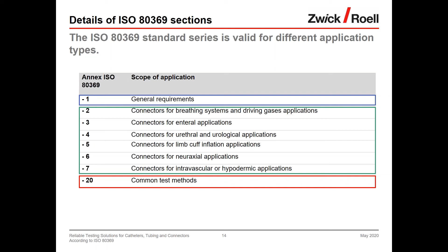If we are talking about the most common one, the ISO 80369-20, it is important to know that each specimen has to be assembled according to the standard with a suitable reference connector before the test sequence starts. In the past, these two test sequences had to be carried out separately. The big advantage of the ZwickRoell solution is that the workflow can now combine these steps, assembly and testing, in one procedure. I already heard from our customers that they save time and reduce failures by repeated handling of samples, and therefore money.